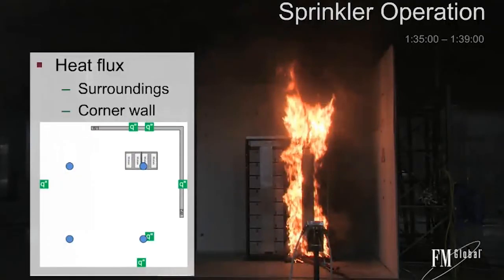This here is a plan view of the same setup. You can see the W1 wall and W2 wall. Those are surrounding the energy storage system. These would represent walls in a real facility. The reason they're there is, first, I want to see what the exposure response is. How much heat does this fire push towards those walls?